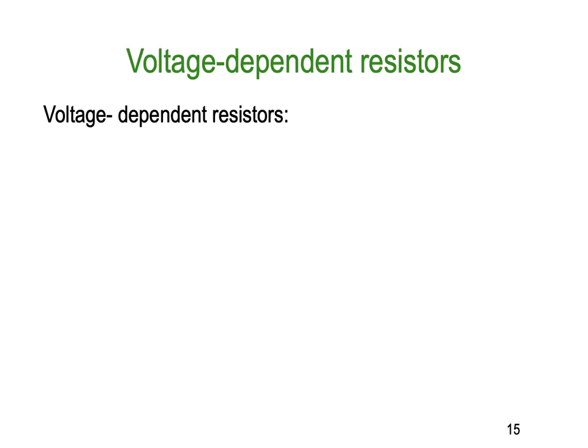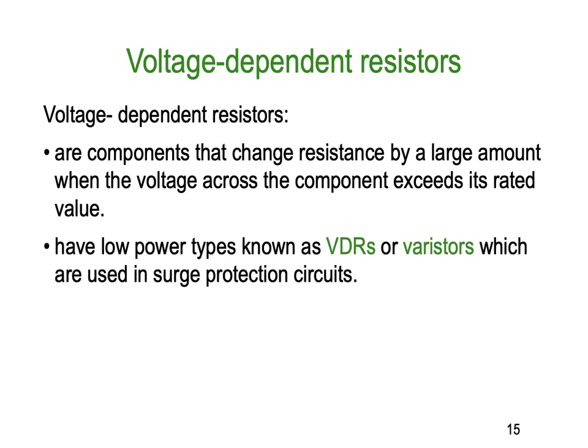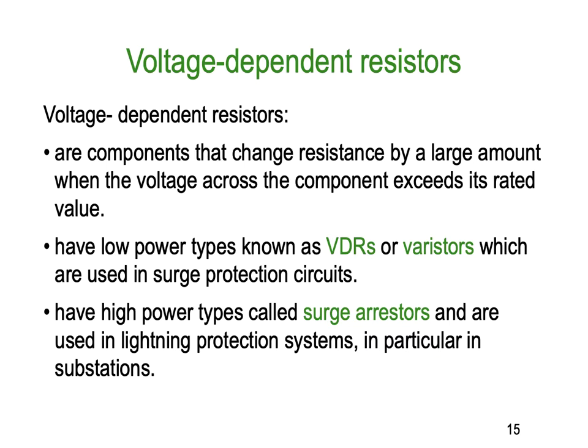The voltage dependent resistor (VDR) is used in protection systems. VDRs are components that change their resistance by a large amount when the voltage across them exceeds the rated value. Low power types are known as VDRs or varistors, used in surge protection in small appliances. High power versions are called surge arresters, used for lightning protection systems in large substation applications. Both are VDRs — varistor for small appliance applications, surge arrester for large energy applications.